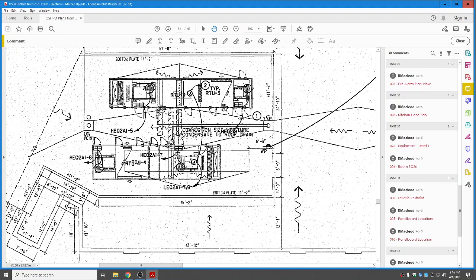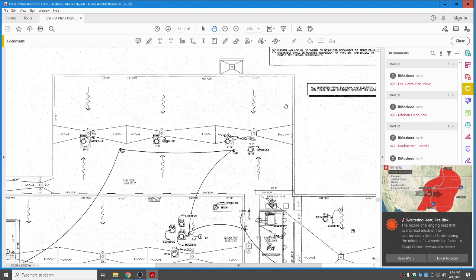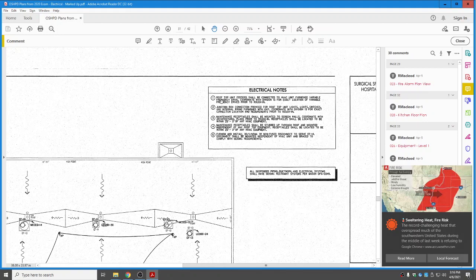We see a motor here on the left side and another motor on the right side. We have a junction box. We have a 2, and also a number 1. Let's take a look at our notes on this page. Number 1, rooftop unit feeder shall be connected to the HVAC unit furnished VFDs, coordinate with Division 15. And the 2 was a junction box connection, is to be provided for the rooftop unit lights, light switches, and internal wiring furnished within the unit.